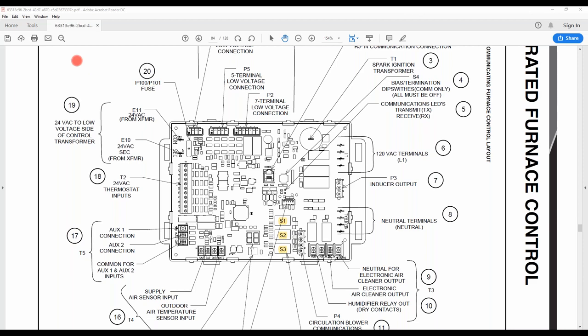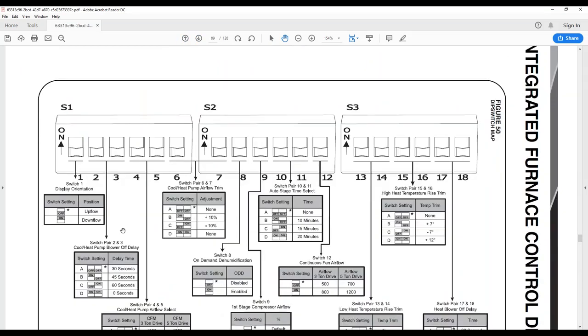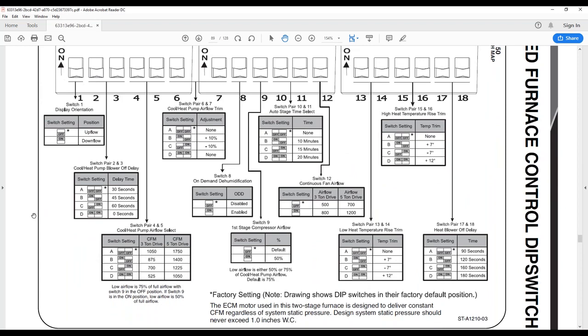We're going to come down here then and go back to those switches. So switch 1 is only for upflow or downflow application. What they're referring to there has nothing to do with the actual design of the furnace. If you're in the upflow position, it comes automatically in the off position, and that is your error codes on the gas furnace, whether they're turned upside down or right side up. If you have an upflow application, leave it in the off position. My example is going to be a code 59. In an upflow application, when it is in the off position, you see it as a code 59.